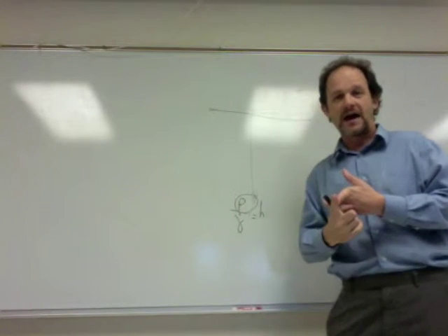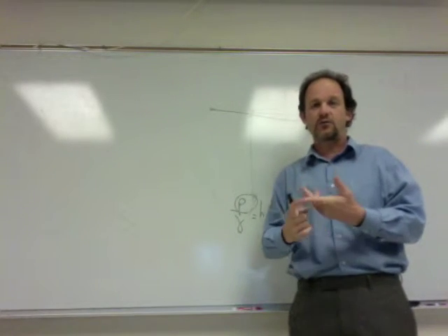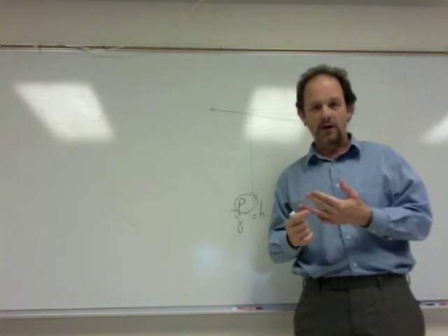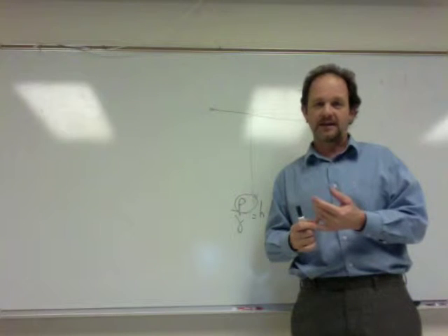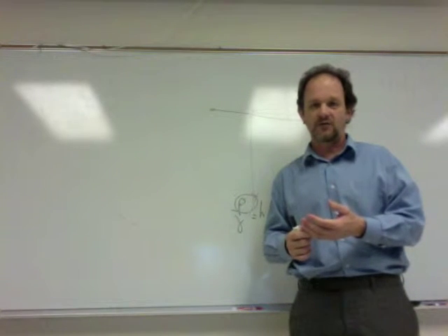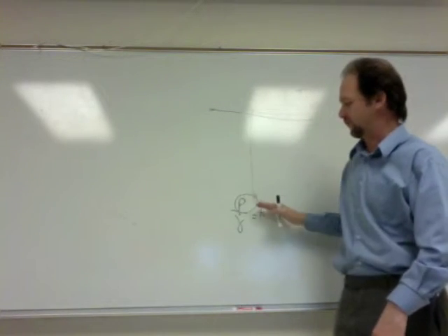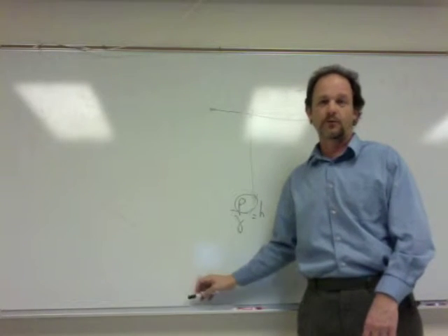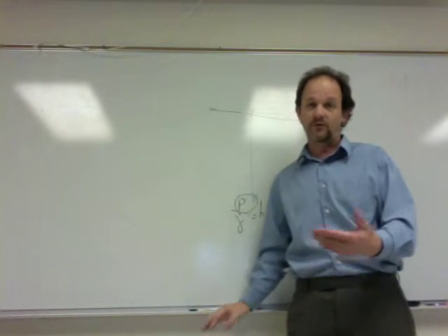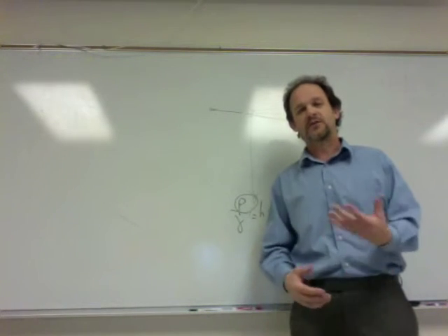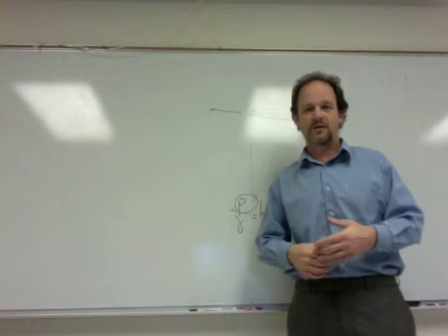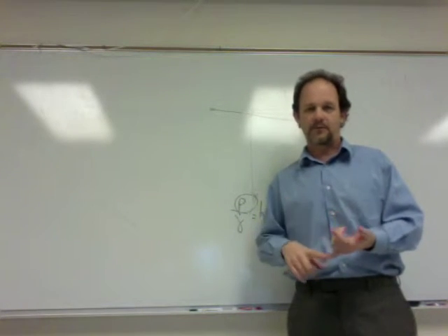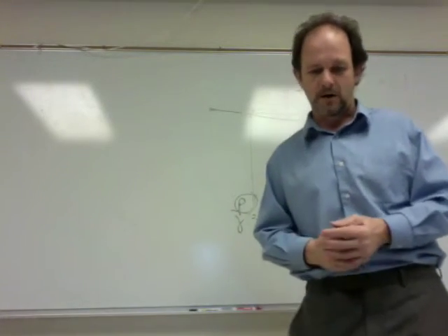Since you know the velocity, for the reason that you knew the flow from the problem two previous, and you know the area of the pipe, that gets you the velocity. If you know the velocity, you can plug it into this equation here because you know the Reynolds number, get a friction factor, and then you can calculate using Bernoulli's equation. And Bernoulli's equation for us, at least in the short term, is going to be plugging it into that calculator when you're given the inputs of friction factor, head, length of pipe, diameter of pipe, and see what you get for output.